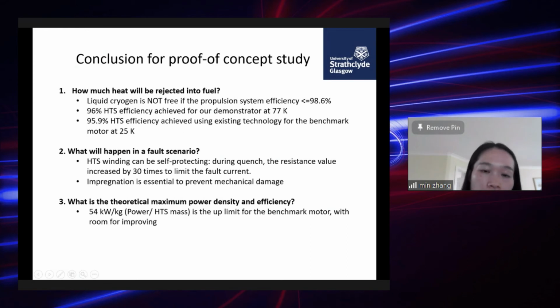And what will happen to a superconducting machine in a fault scenario? We found that HTS windings can be self-protecting, because during quench the resistance value of the winding automatically increases by at least 30 times to help limit the fault current. On the other hand, we want to provide impregnation for these windings to prevent mechanical damage. And finally, based on our baseline design, the theoretical maximum power density we obtained for the 2.67 megawatt machine is 54 kilowatt per kilogram.